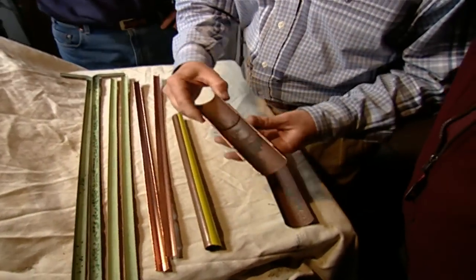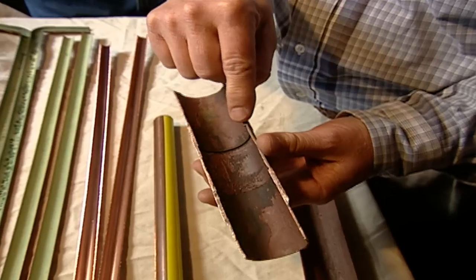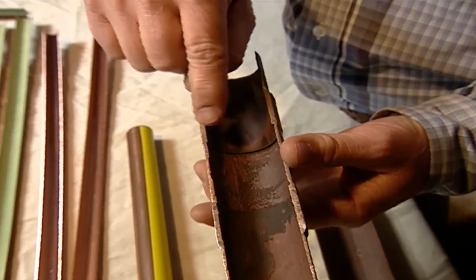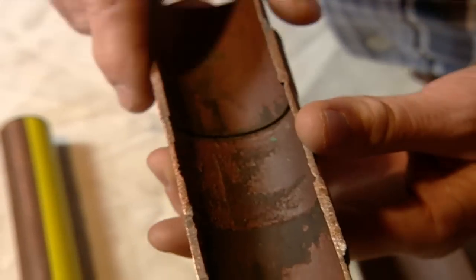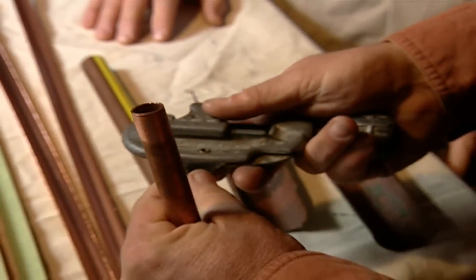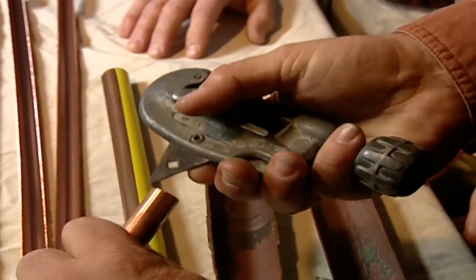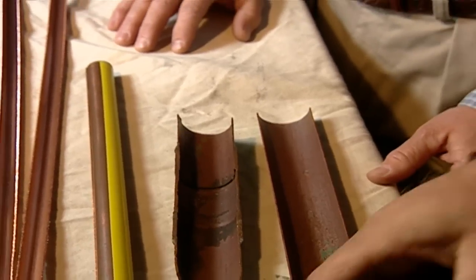Another related problem is where the ends of the pipe are not properly prepared in making solder joints. If the burr at the end of the pipe is not reamed to remove it, we have local turbulence, and that can cause another related erosion corrosion problem. That is so important. Most people have no idea that on every tubing cutter there's a reaming tool made to be able to open up that pipe so you won't get an impediment. That's right, very important. All right, what else?